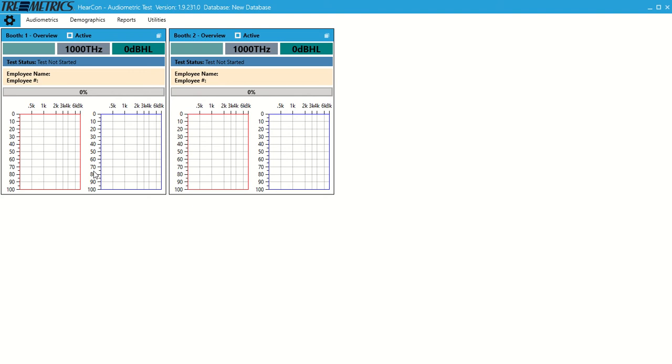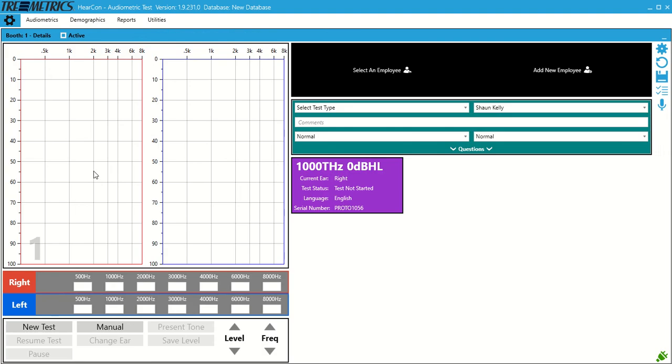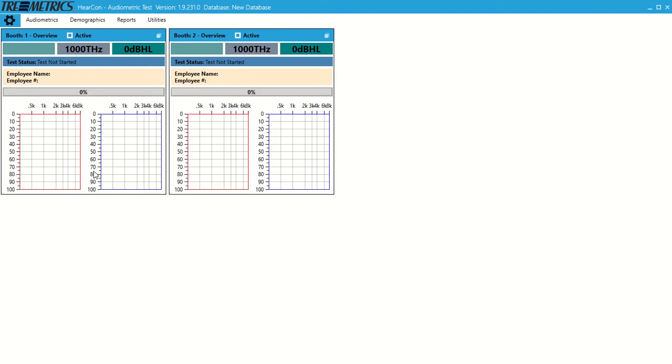With the group test on the RA-660, you can hot swap the instruments. Right now I'm going to unplug an audiometer, and then it goes back to the single test view. If you were doing single station testing only, this is the only screen you'd see. And then as soon as you plug in a second audiometer, it goes back to the tile view.